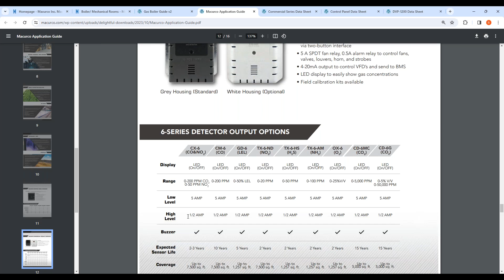You also have the 4 to 20 milliamp output, which a lot of controls contractors use for automation purposes. Here's where the next segment of our business at Macurco has really taken off: the expected sensor life. When I first started, sensors would expire and people would just want to replace them. Now you have field replaceable sensors, which also entail calibrations. So for any customer base looking for continued RMR or a continued service contract type business, these units are very, very good.